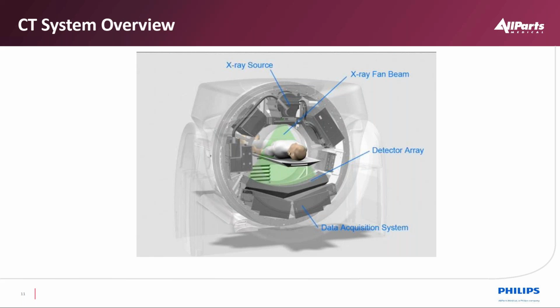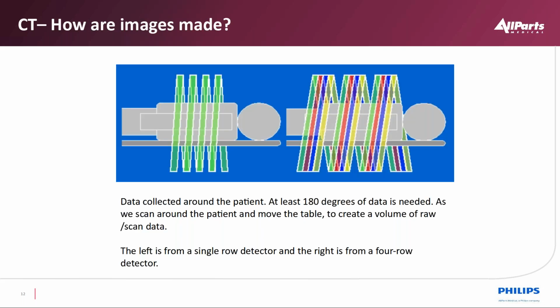EBT, as it's known, was best done with cardiac studies before scanners got fast enough in gantry rotation to be able to take over that duty as well. So we have the X-ray source, the fan beam represented in green, and a detector array. The detector array is a crystal that will take the X-ray photon and convert it into light for a photodiode to pick it up, and then that photodiode will be digitized.